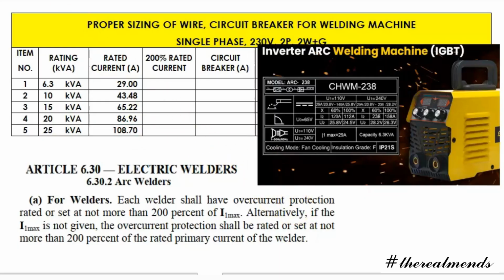So 10 kVA is 43.48, 15 kVA is 65.22, 20 kVA is 86.96, 25 kVA is 108.70 amperes. From this we can arrive at the rating of the circuit breaker, also known as overcurrent protection. Again, refer to our PEC. If we have the rated current, let's multiply it by not more than 200% of the Imax.